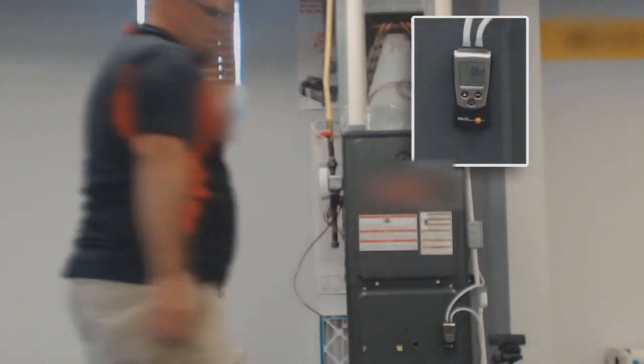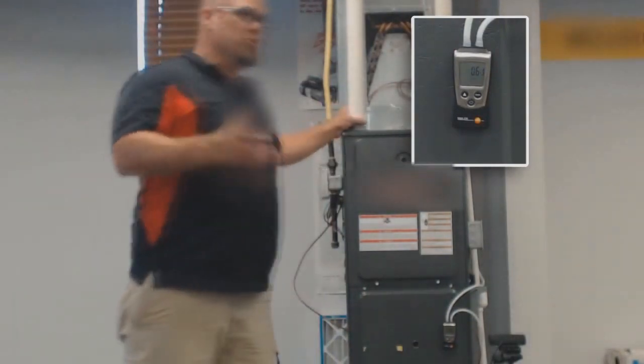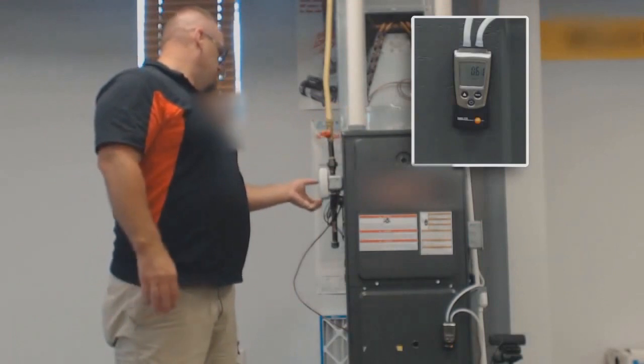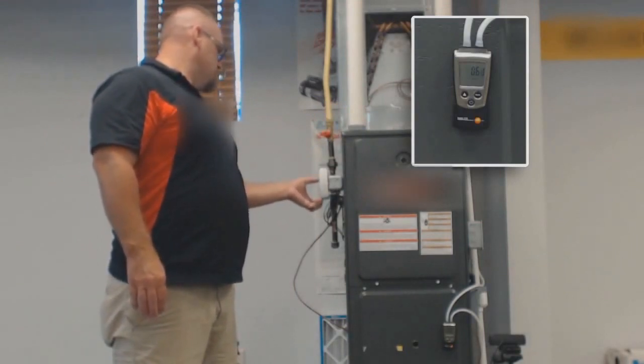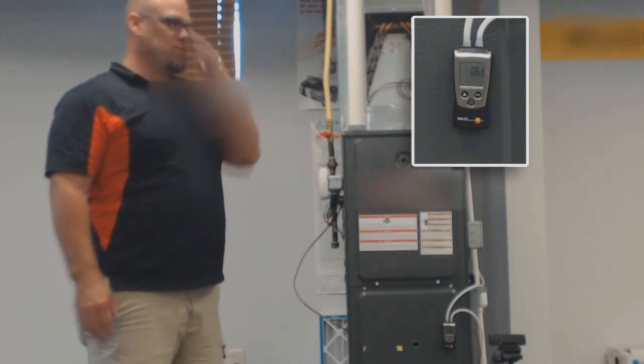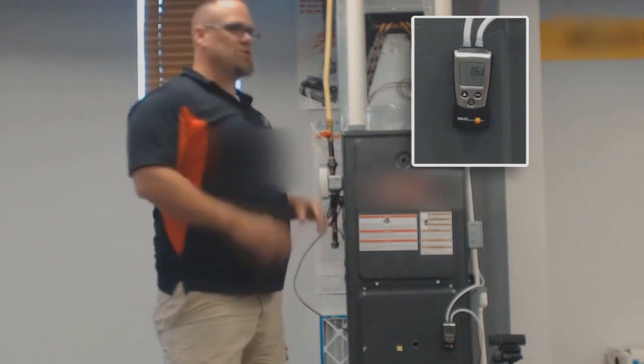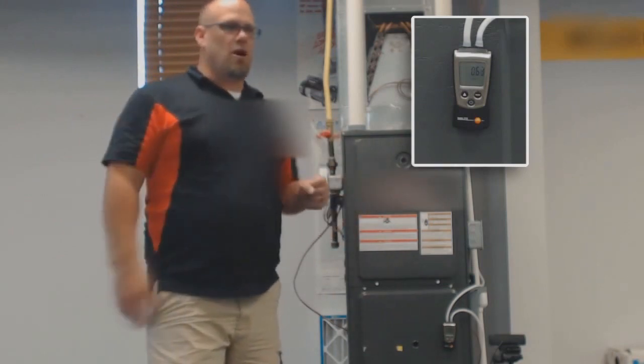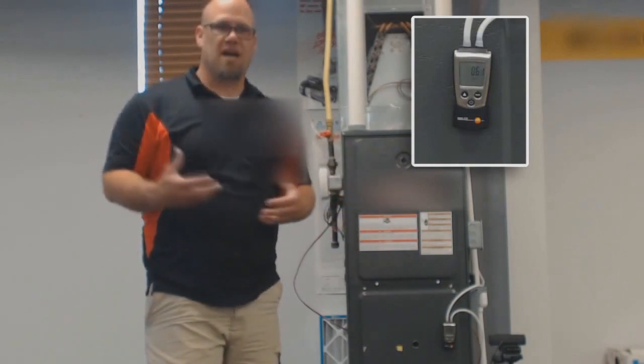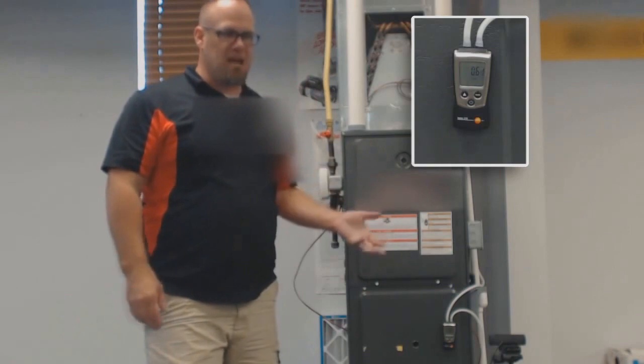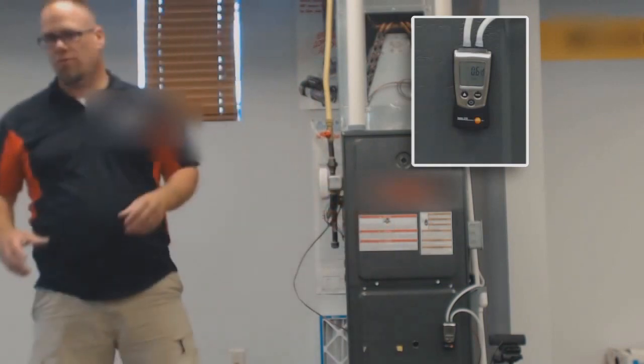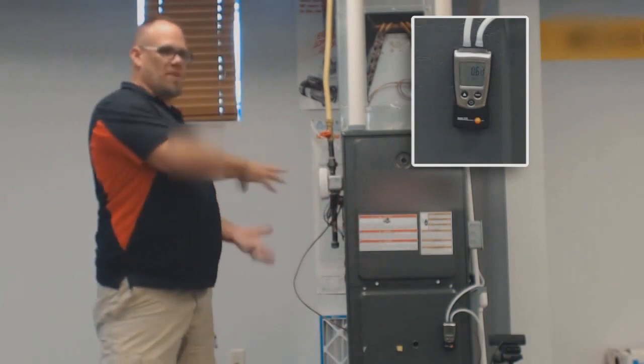So that amount of airflow would mean that we wouldn't get the right amount of cooling for what we're looking for. We've got to have somewhere around 400 CFM per ton, so that airflow per ton is super important. If we left it on high speed and went in and checked our temp drop across the coil, we would notice our temp drop across the coil wasn't very good. We would also notice when we're checking our charge that our superheat or subcooling would be off, depending on the type of metering device that we've got. So we would have to go back and adjust the charge to compensate for the poor amount of airflow.